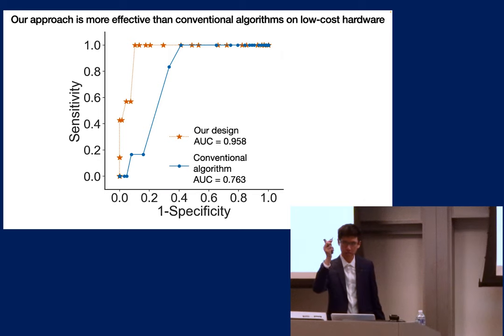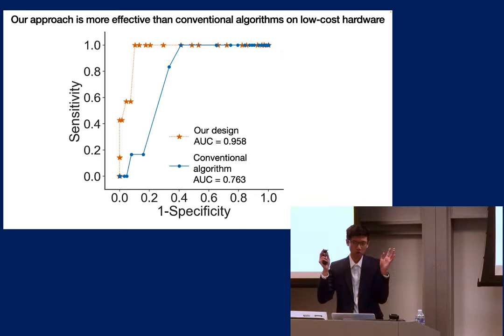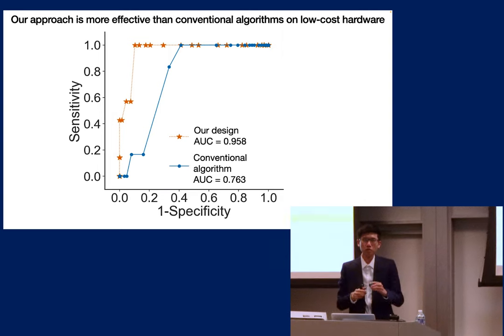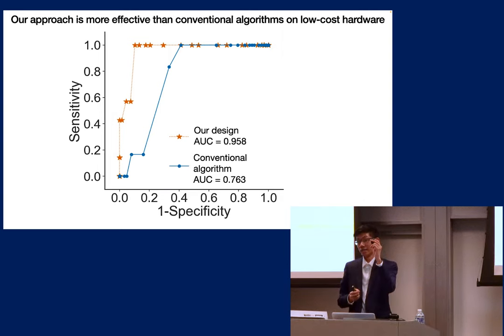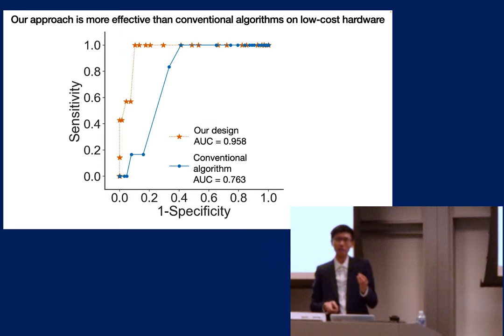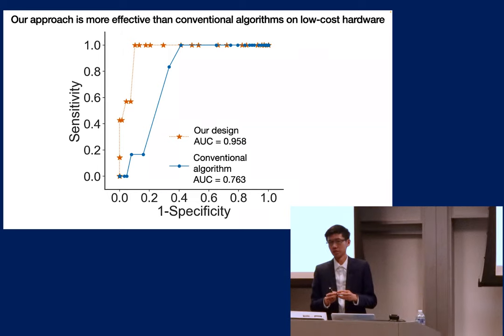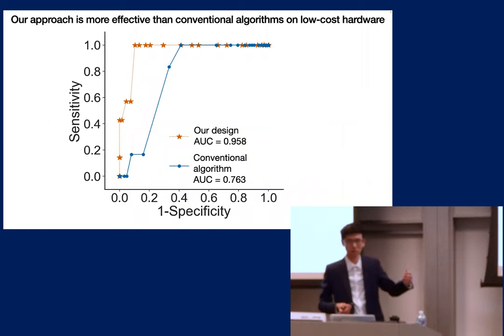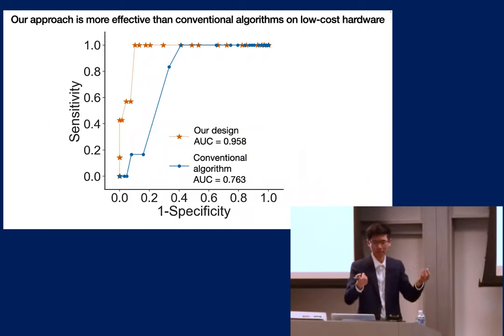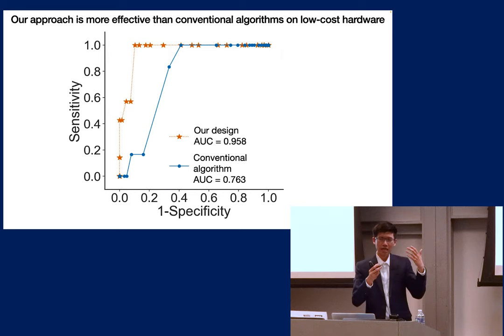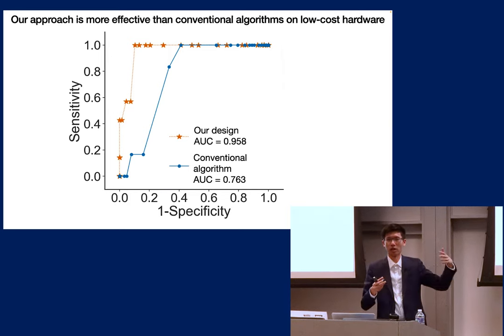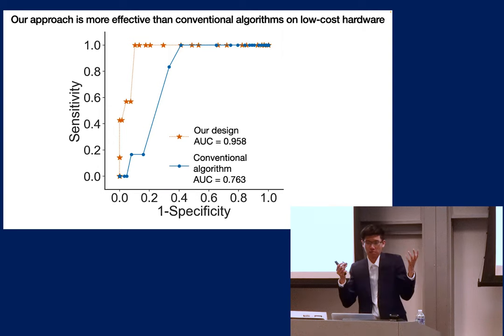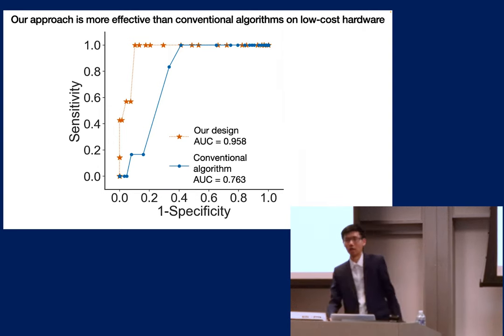For this specific system, it's using a custom speaker and microphone, but it's off the shelf, like $1 or $2, nothing special. But if you were to do calibration - let's say it decayed over time, a year from now the acoustic response is not as good - what you could do is calibrate for the volume, because if the volume you send in is not the same every time, you're not going to get the same signal from the cochlea. So you could put it in a calibration tube and make sure whatever you receive from the microphone matches some reference value. You could do something like that to ensure calibration.